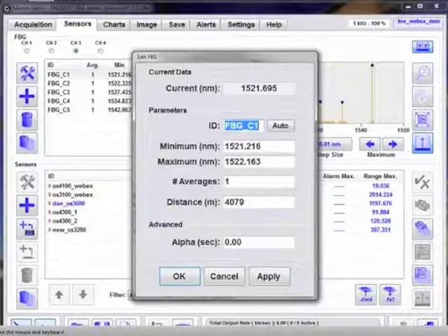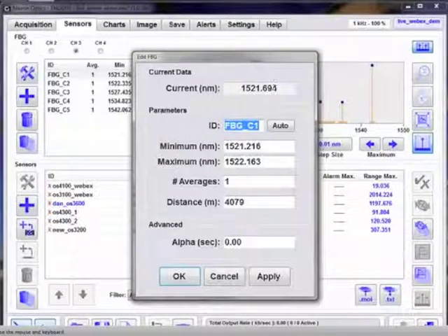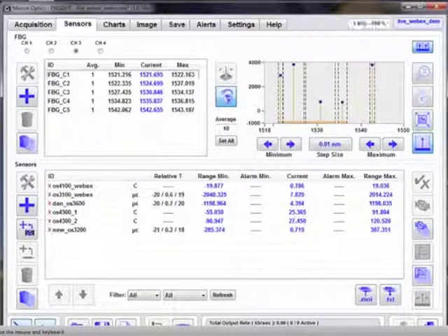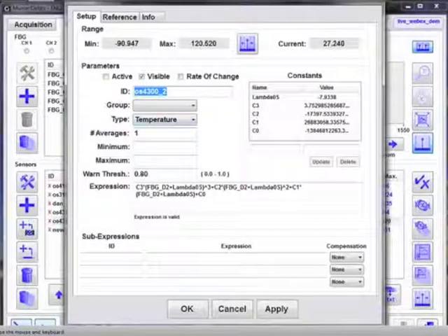So in our case, where we reference a 4100, a 3100 and a 3200, both reference the same 4100 sensor, that could be averaged at that FBG, for example, and then the strain sensors themselves could be independently averaged to give the 3100 a particular repeatability and time response, and the 4100 a different repeatability and time response. If one was being used to monitor dynamic changes, and the other was being used to monitor very small static changes, then you can independently set those sensor averages while retaining the same averaging on the temperature compensation sensor, which could be done at the FBG level. Yeah, it's averaging.